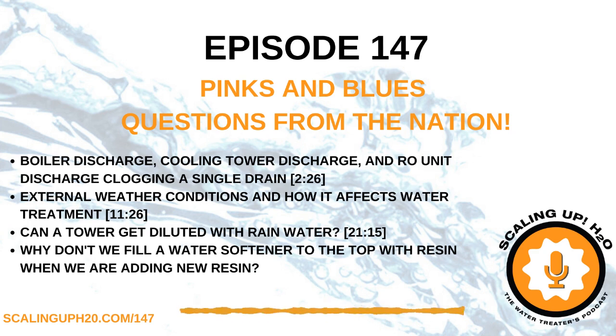So maybe this will work: maybe you can install a tank so all three bleeds go into this tank, and you size the tank so it can hold more than it needs. The bleed goes into the top of the tank, and at the bottom it goes to the drain. You size that drain pipe coming out of the bottom of the tank so it won't overwhelm the drain, meaning you need enough capacity so that however long it takes to drain, while the tank is filling up, it doesn't overflow. So you're going to have to do a little math there.